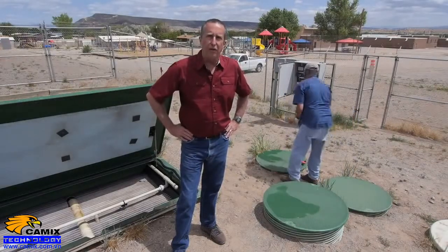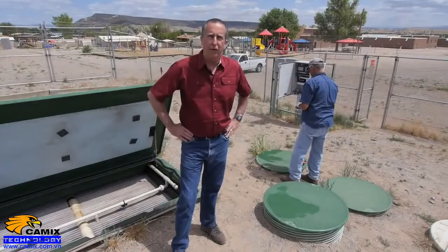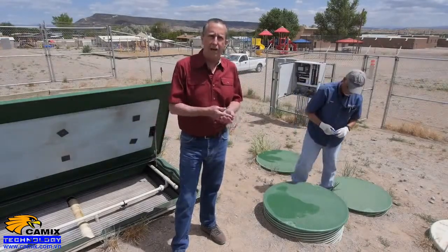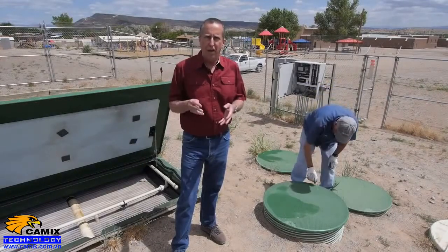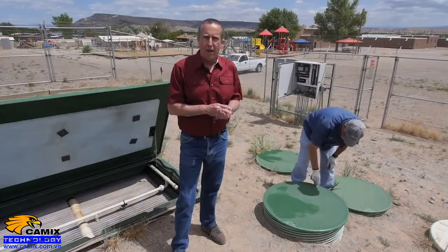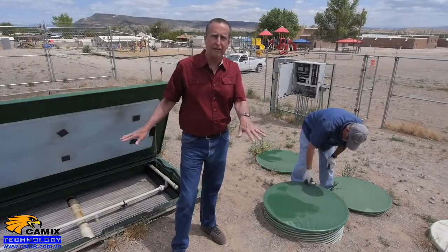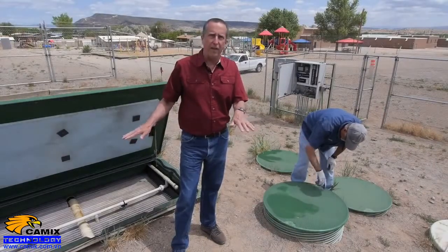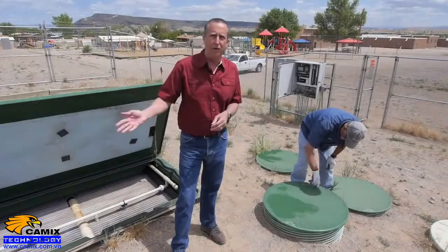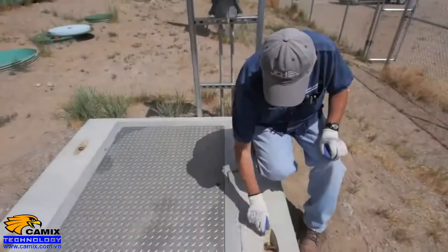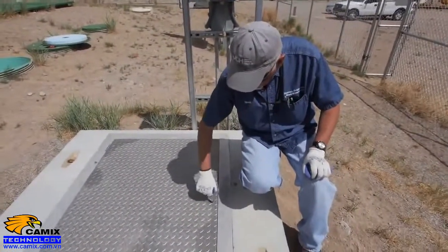Also, in a situation such as a school where you have a high level of nutrients coming in during the school year when school's in session, and then school lets out during the summer and the nutrient load drops to almost zero, sometimes the operator will have to put these on a recirculation mode to keep the biomass that's here healthy, or perhaps even add an additional carbon source over the summer, such as dog food or some other source of nutrients.